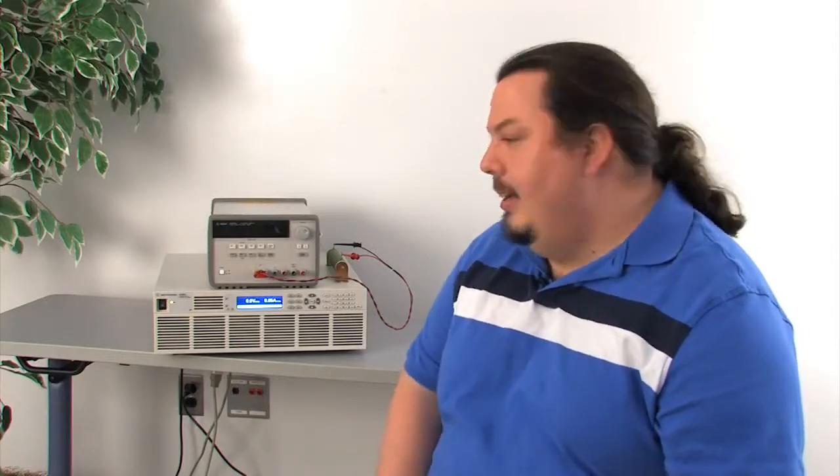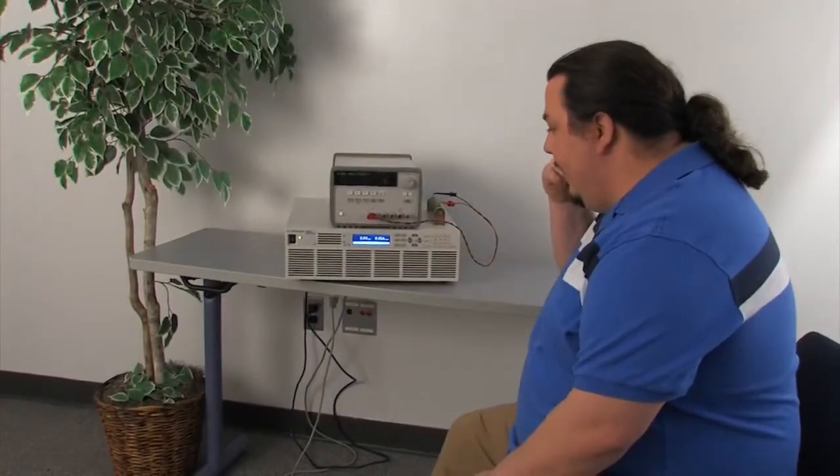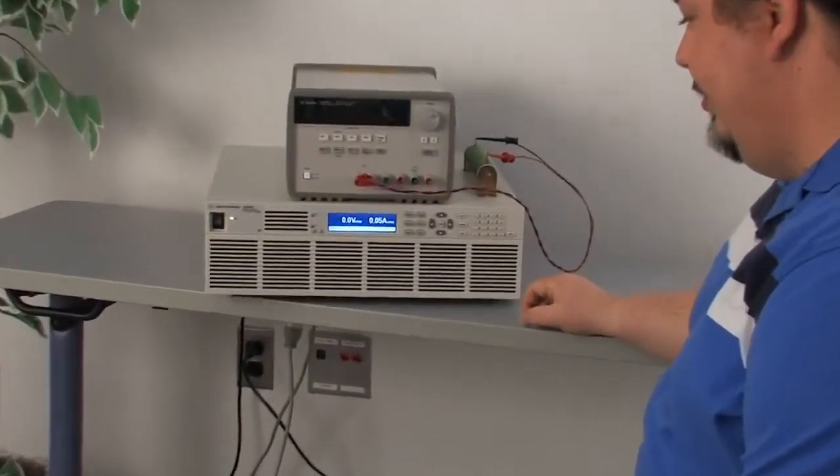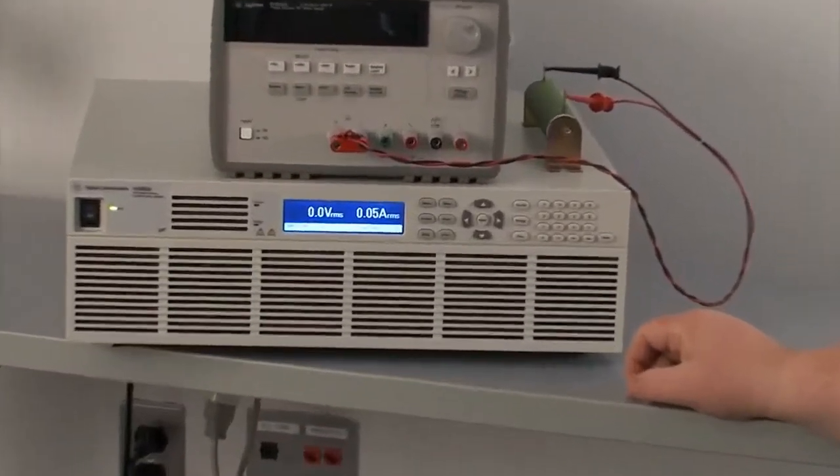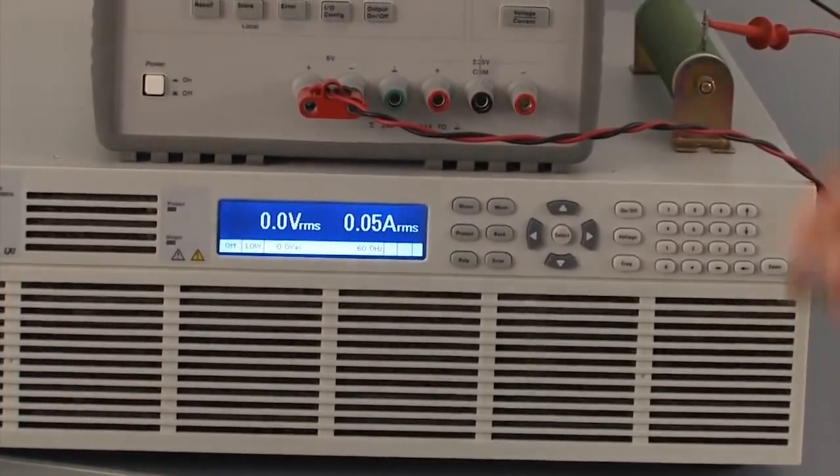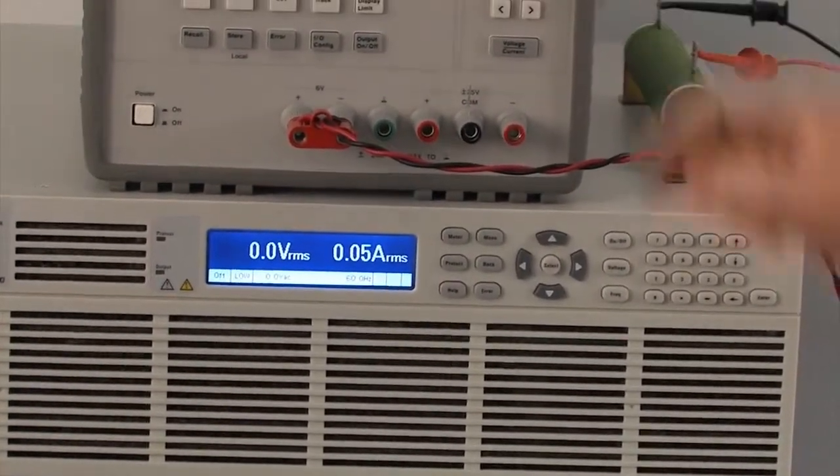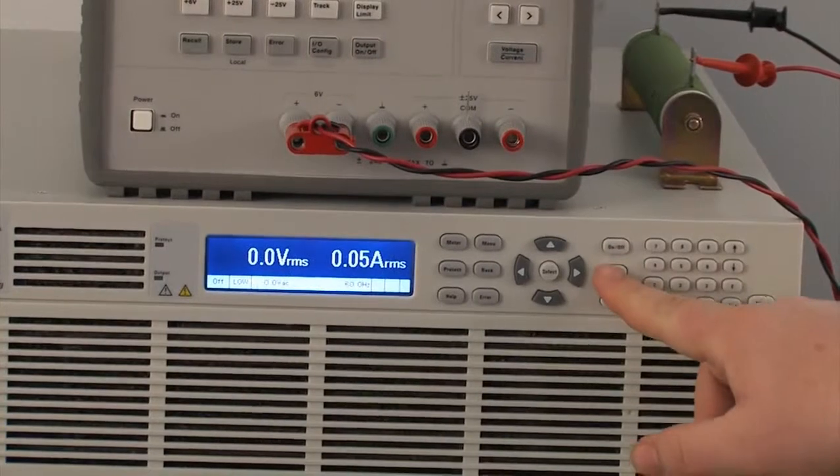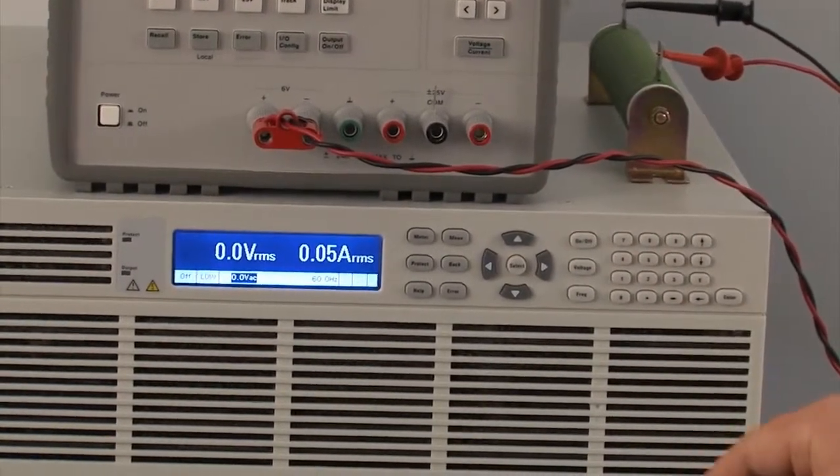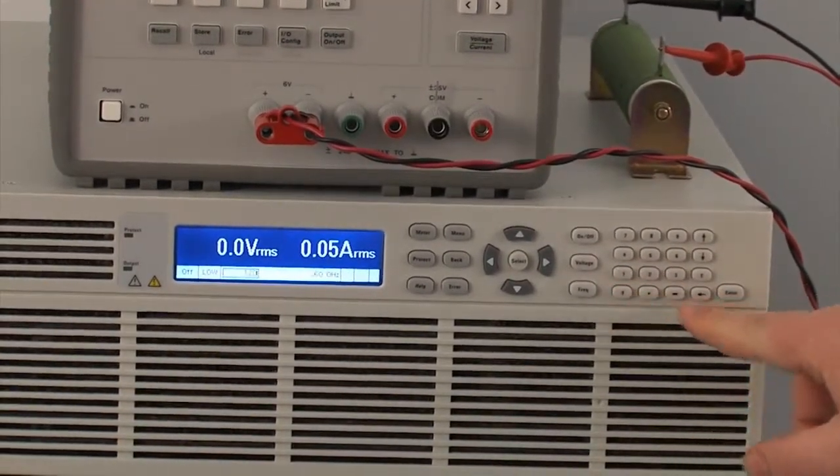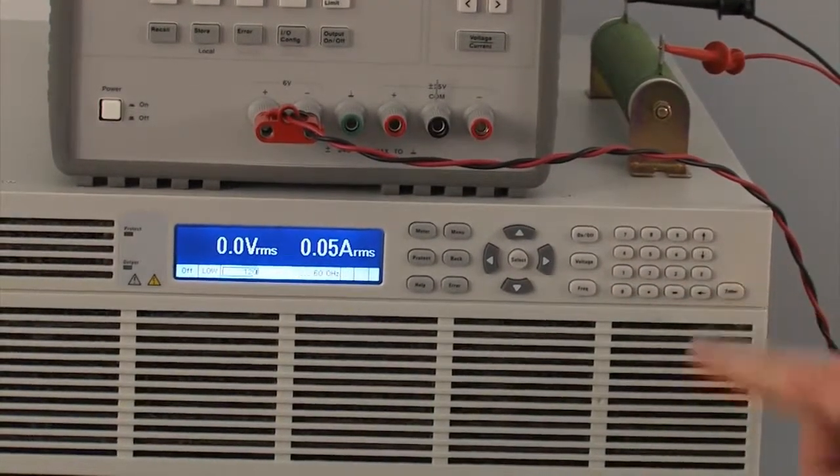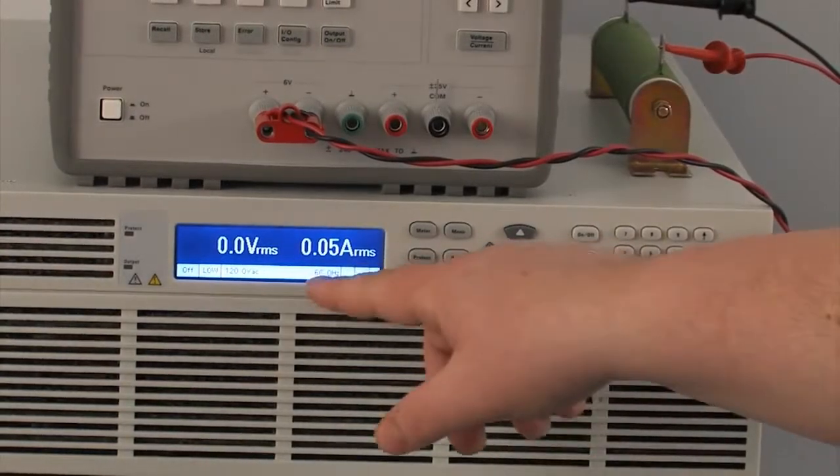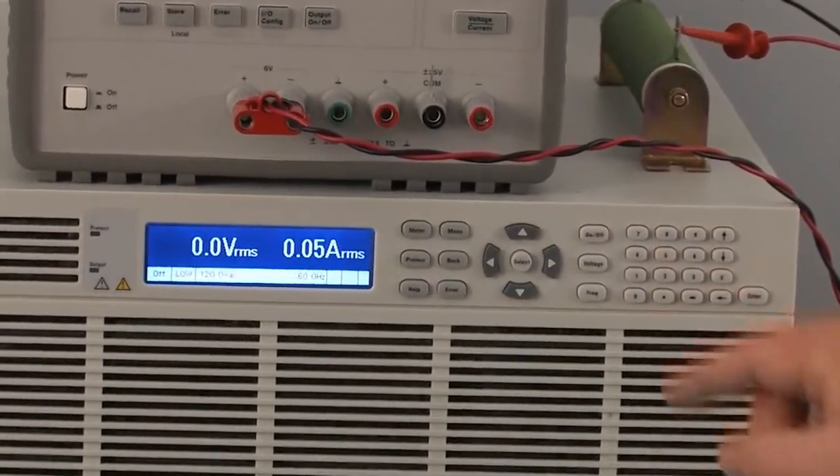So I'm going to get into it and start talking about the metering and to show you how to make measurements. You can see here, this is the standard screen you get when you start the AC source. So the first thing we're going to do is get our DUT running. We're going to set the voltage. This is set up to work in the US, so it's a 120 volt unit and 60 hertz. It's already set to 60 hertz, so we'll leave it at that.